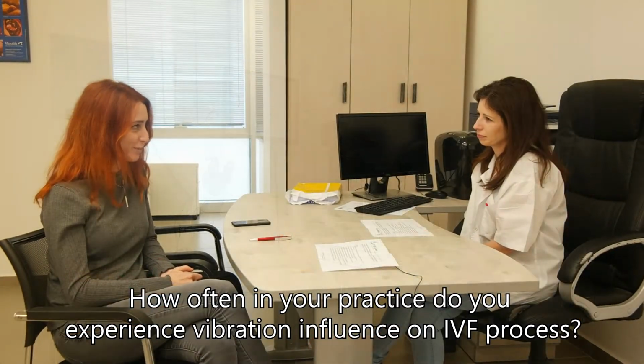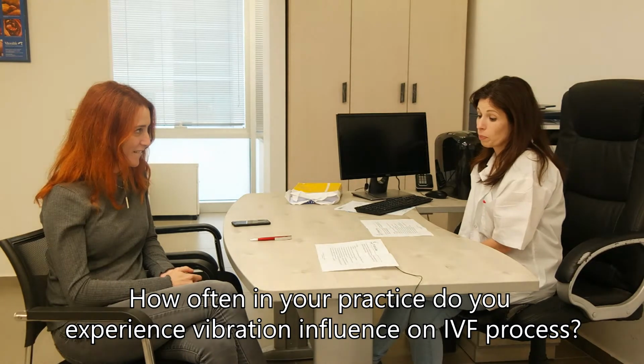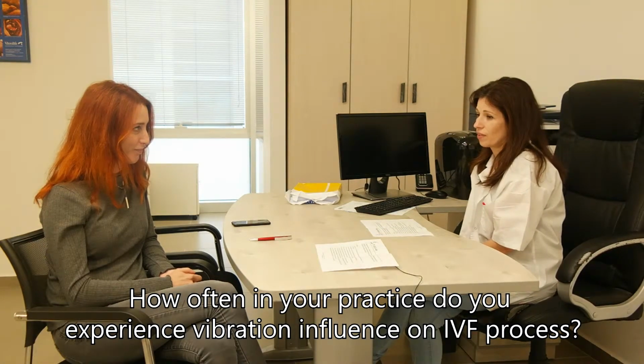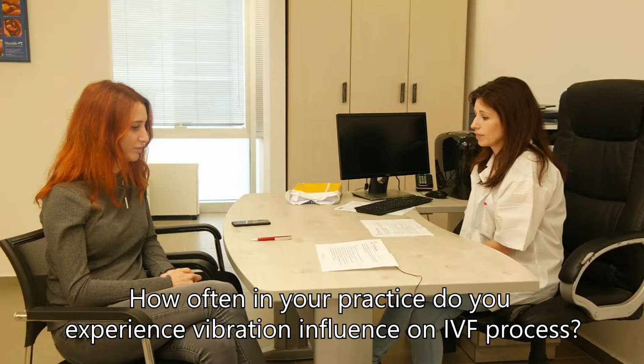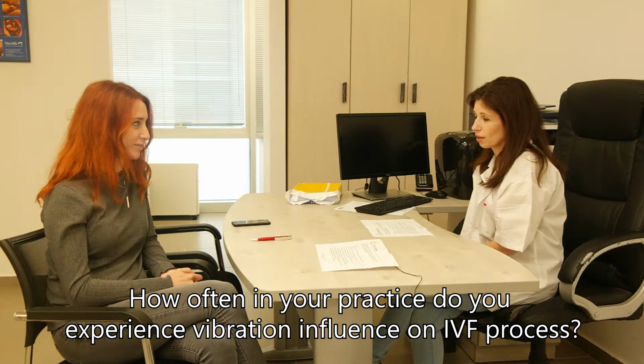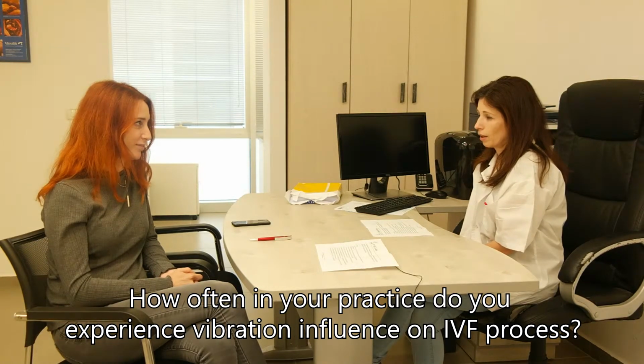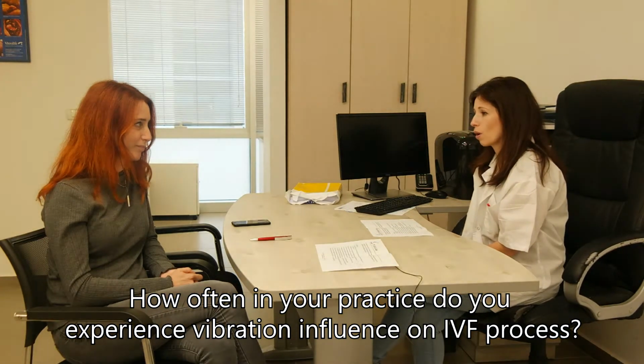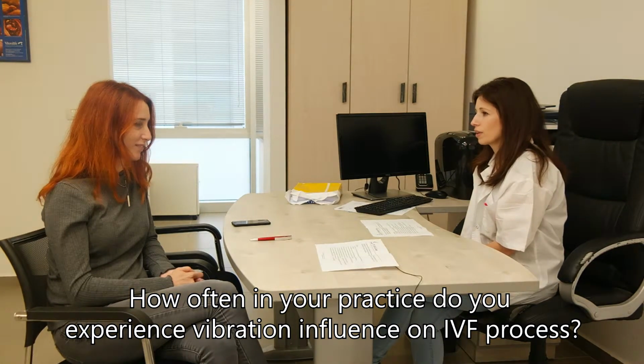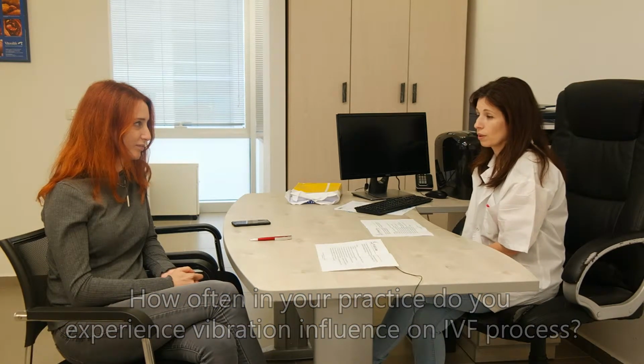How often in your practice have you experienced vibration influence on the IVF process? The IVF process as a whole is very, very influenced by vibrations because we work in high magnifications, with micromanipulations. The sizes that we're talking about and the distances that we're using while doing the fertilization are microns. And when you work in high magnification under a microscope in microns, everything that happens in the room has influence on the vibration and on the quality of work.